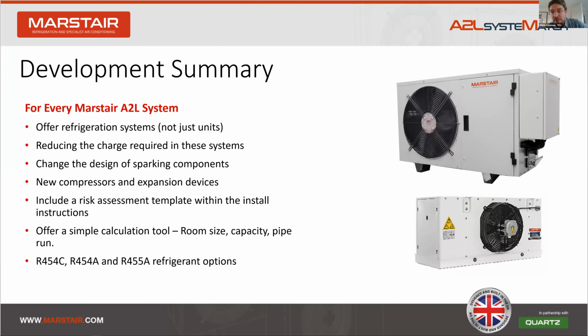So, just a quick recap on the developments. We offer cold rooms. We offer cold room systems, not just individual condensing units, which is important. It's only through this that we can know the charge and calculate the free volume requirement at the specification stage. Secondly, we've reduced the refrigerant charge level to a minimum. This ensures the maximum pipe run relative to cold room size is available. We've changed the design of our units to ensure compliance. We are using compressors and components that are approved for use with A2L refrigerants. Again, this helps us with our 5-year parts warranty. We include a risk assessment template within our instructions to help contractors with their installation. And the A2L system match will be suitable for a family of refrigerants: R454C, R454A, and R455A.